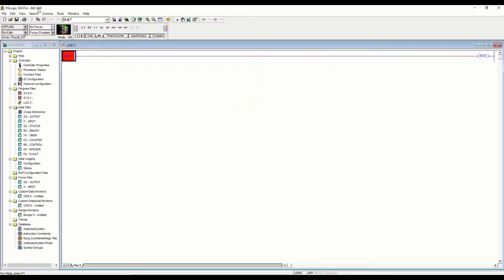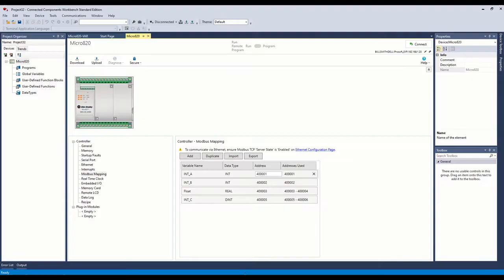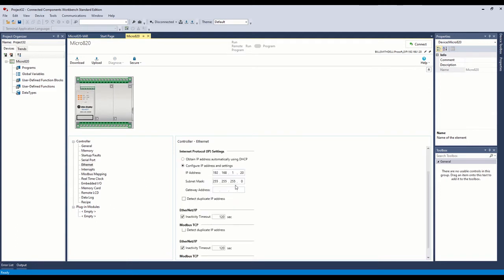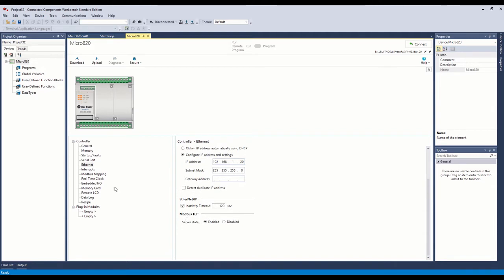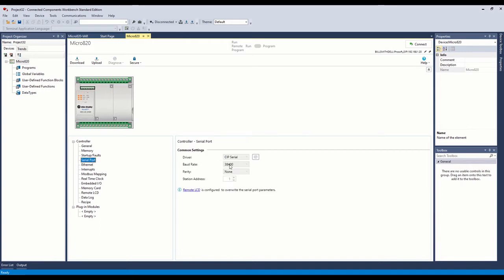Here we have our blank MicroLogix 1400 project and we're just going to start from scratch. The goal is to set up the MicroLogix 1400 as our Modbus TCP master. For the Modbus slave device, I have a Micro820 controller. There are two things you have to do on it to enable that functionality under the ethernet — we're using TCP so you want to enable the Modbus TCP server. We could also do this over serial as well; both of these devices have that ability.